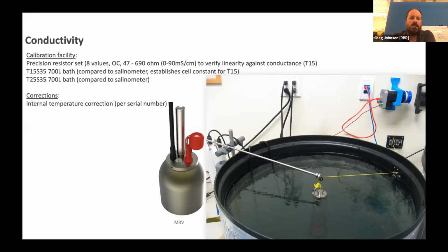And then finally, to establish the overall slope temperature dependence, we take a second measurement at T25. However, that temperature dependence of the slope is something that's intrinsic to the unit and doesn't change over time. So you don't need to do that yourself if you're ever recalibrating. You can simply take an air measurement and a single water bath measurement, and that's sufficient. And the corrections that are applied are this internal temperature correction, which is per serial number.